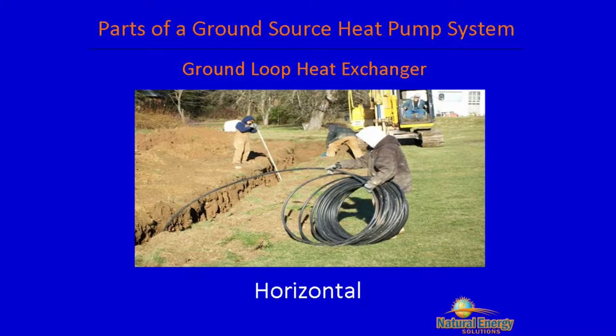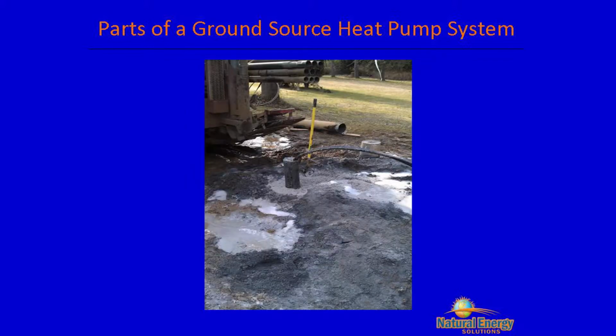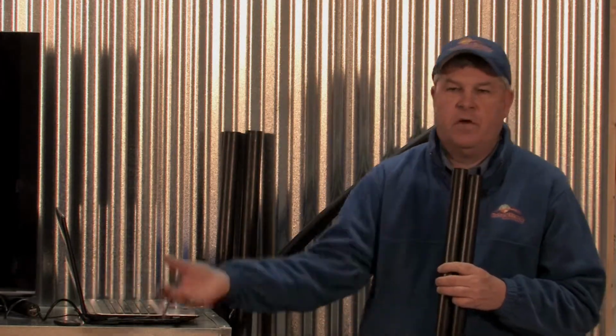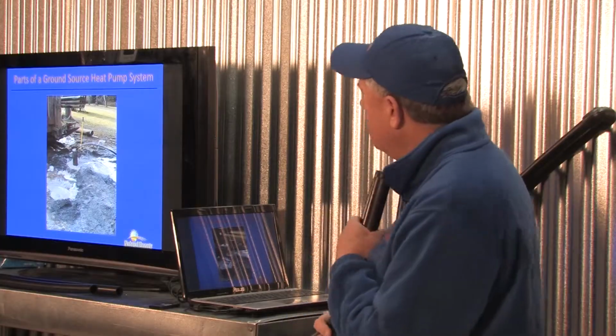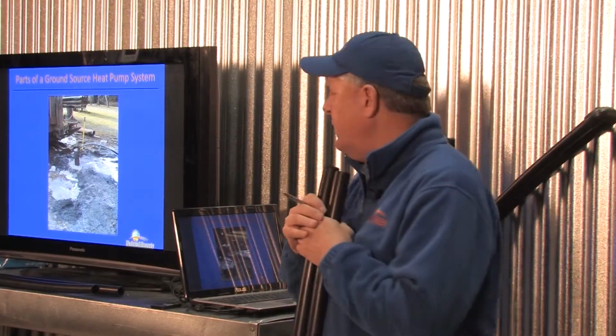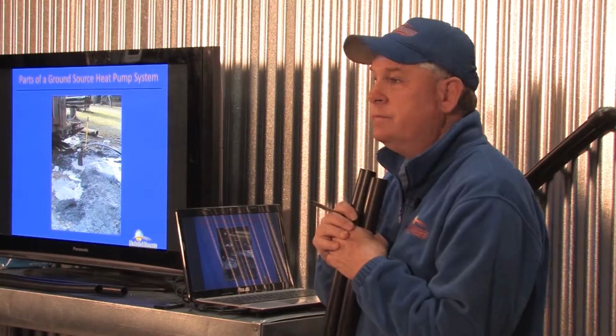Well, a ground loop heat exchanger can be horizontal. I can lay this pipe in flat. If you don't have enough room, then we have to go down. A vertical system, a vertical heat exchanger. How deep do these go? Generally anywhere from 150 to 500 feet. But it could be 1, 2, 5, 10 holes. The number of holes is dictated by how much heat we need for the house. That particular one, I believe, was about 250 feet deep.